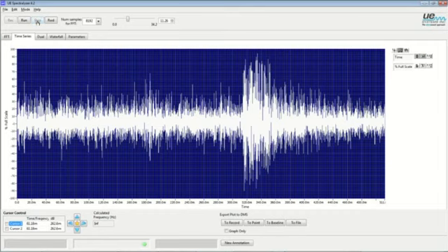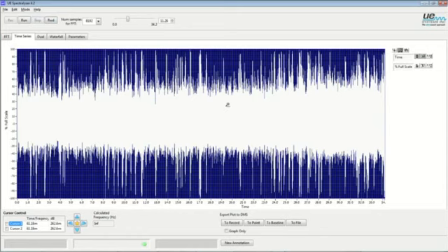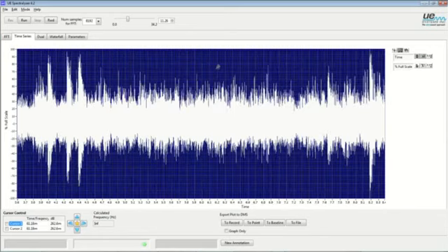Not just in the tonal quality, but when we look at the time analyzer for the entire 35 seconds, we see this broad band of white noise has become thicker, and we have more discharges more tightly compacted. This is hard to see on the full view, but as we zoom in, you'll see the discharges of energy are occurring more frequently.